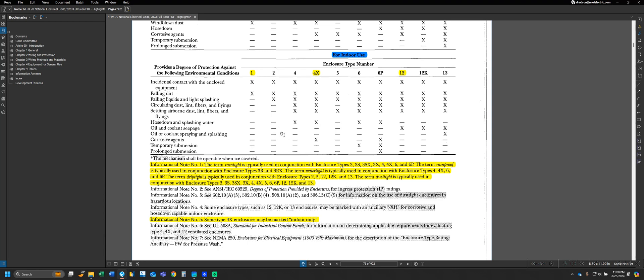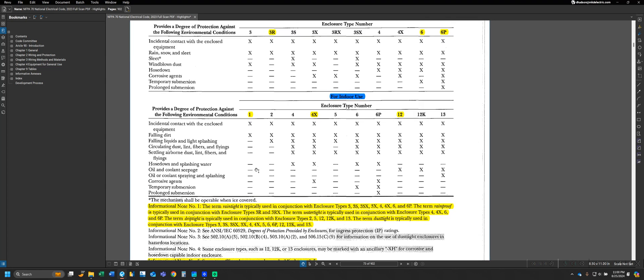If we were to look at comparison of a 4X enclosure, another common type of enclosure, we see that it offers the same protection as a NEMA 1, but has all of these additional protection types that are listed for the 4X enclosure. We can even see amongst all the enclosure types for indoor enclosures, a 4X and a 6P are the only enclosures that protect against corrosive agents. It's our job as the electrical professional or the electrical installer that we have to coordinate what type of enclosure we're going to need based on what type of environmental conditions we're installing them in.